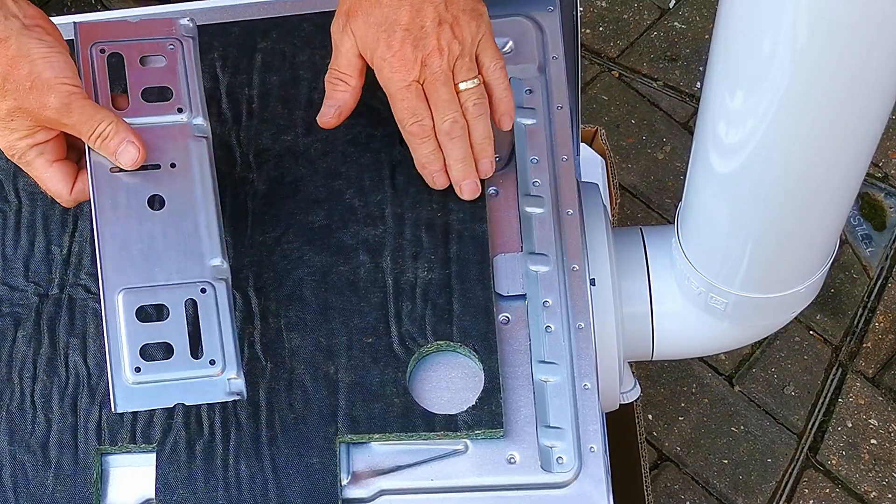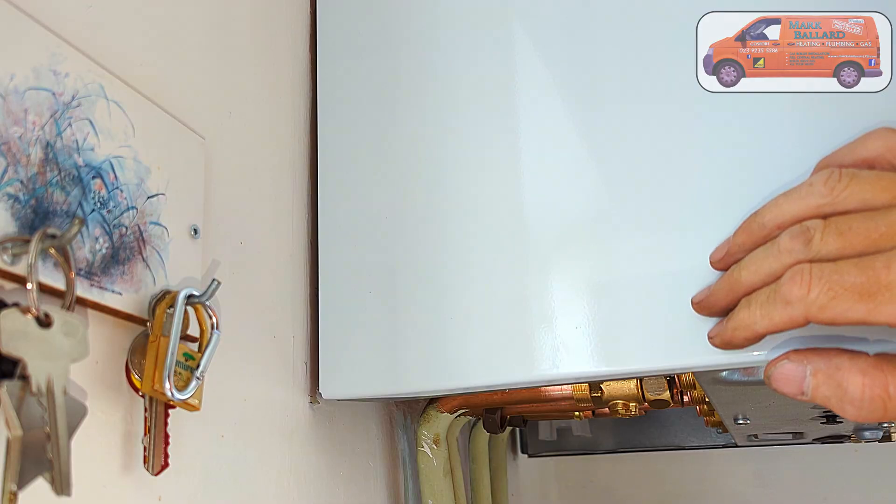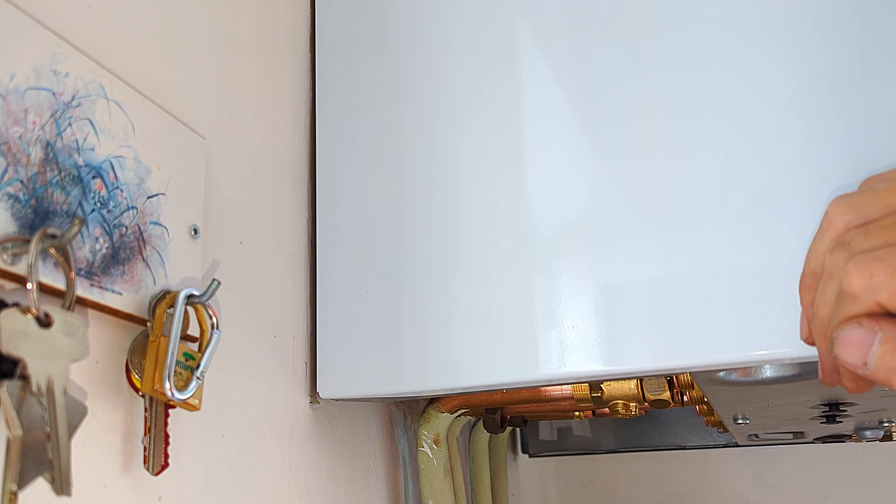In this video I'm showing some issues I've come across when installing the brand new Vaillant ecoTEC plus combination boilers. These new boilers have got a really thick bit of insulation on the back of them and it's been giving me some issues when trying to hang the boiler, and also once the boiler is hung it's kind of springy - it doesn't sit back against the wall, you can push against it and it kind of bounces backwards and forwards.